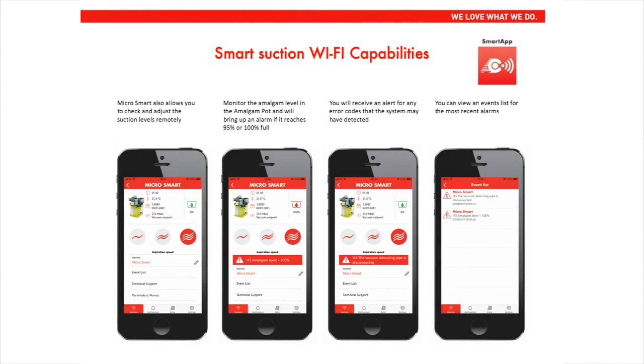MicroSmart also allows you to check and adjust the suction levels remotely. You can also monitor the amalgam level inside the amalgam pot. This will bring up an alarm if it reaches 95 or 100% full. You will also receive an alert for any error codes that the system may have detected. It will also allow you to view the events list for the most recent alarms.